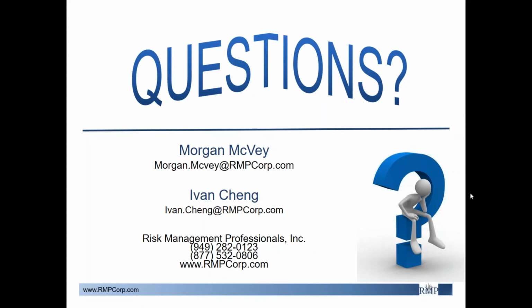Next question: can you exercise rapid verbal approval MOCs without having a specific MOC procedure in place? In order to exercise this type of emergency MOC, you absolutely have to have a procedure in place. There are multiple things that need to be included within that procedure, such as what constitutes an emergency, who is approved to step in and make that decision in that situation, and when the actual MOC documentation will be prepared. These are all elements that will be discussed within the procedure. So you do need to have a procedure in place to exercise that type of MOC.